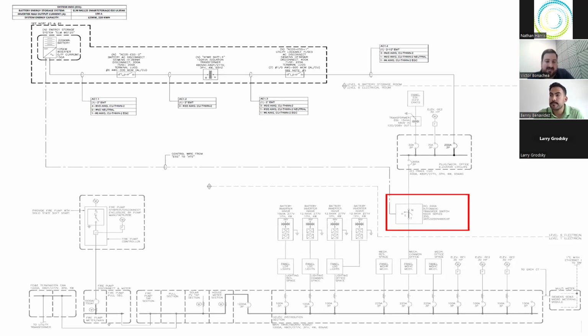Again, because ATSs are not designed for this application. And it's not just a question of how are they listed or terminology or anything like that. They functionally will not work. The reason being that most ATSs on the market by all manufacturers pretty much require power from the source, from a power source, to be able to transfer.